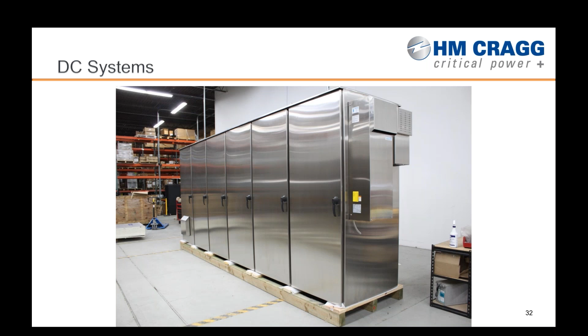And then on the complete opposite side, we are also offering smaller DC systems. So we had a project in Texas for a utility that was upgrading their communications equipment, and they required all of these kind of small cell-esque power systems for their communication equipment. So we deployed about 24, 25 of these systems for that utility in Texas, and it was a Neg 48 DC rectifier system, DIN rail mounted, and 4 high temp pure lead batteries.